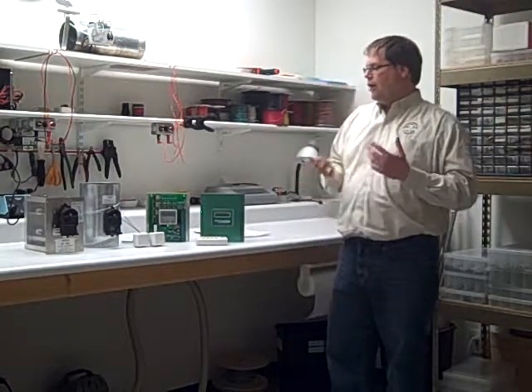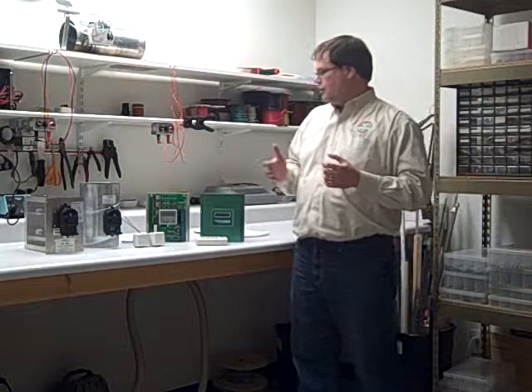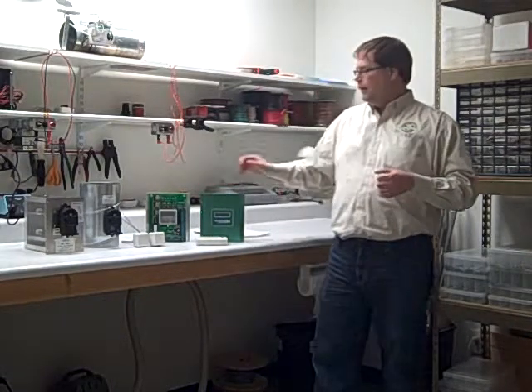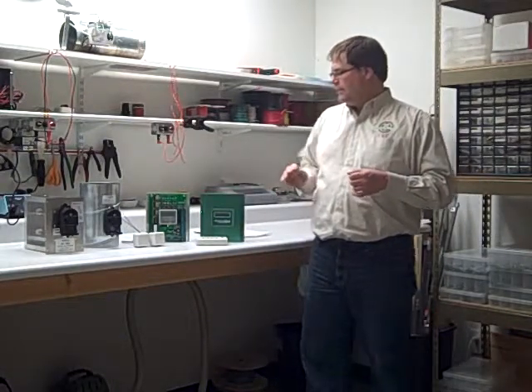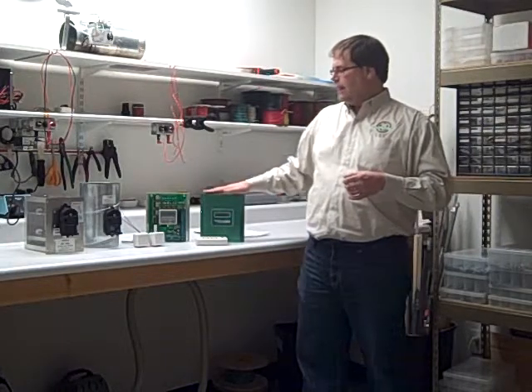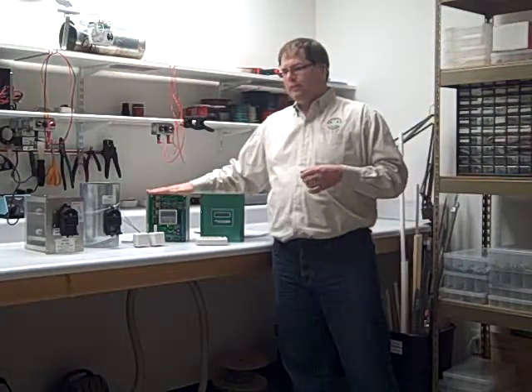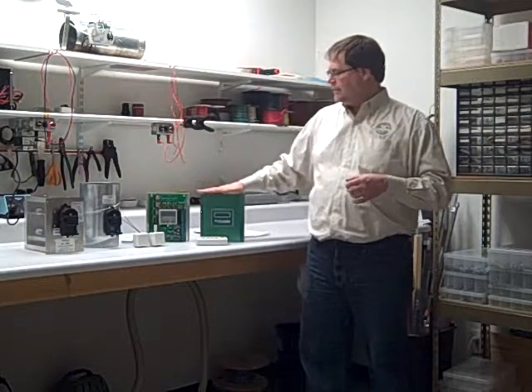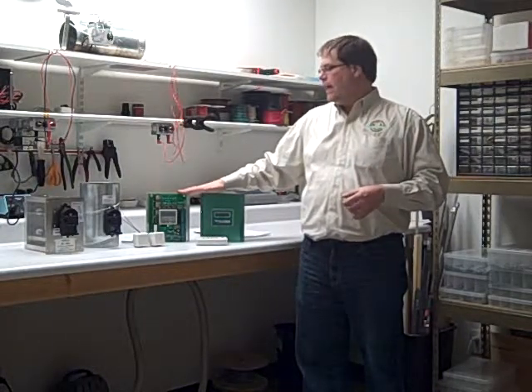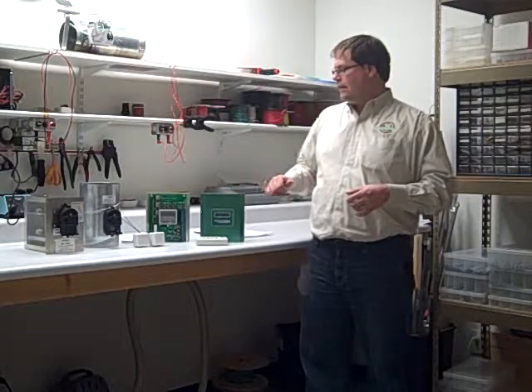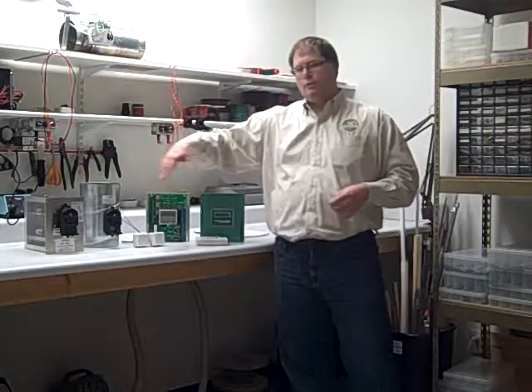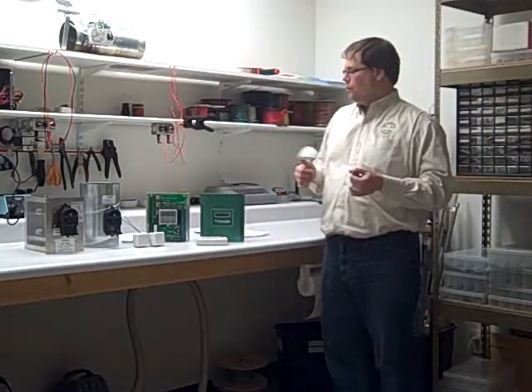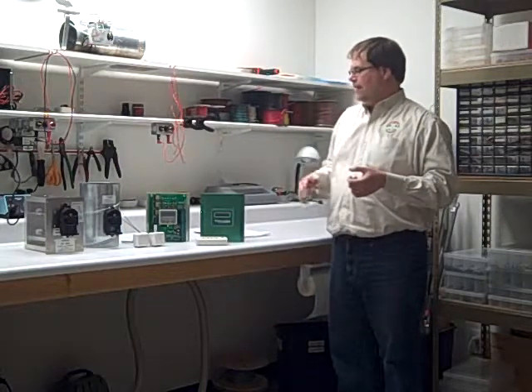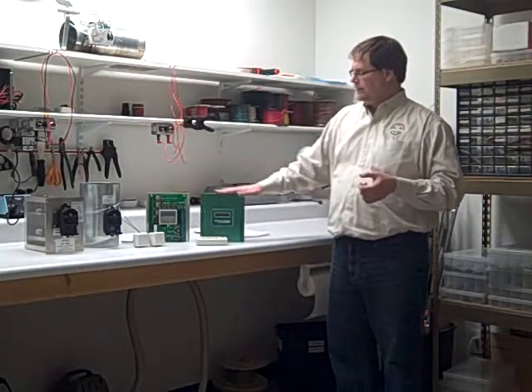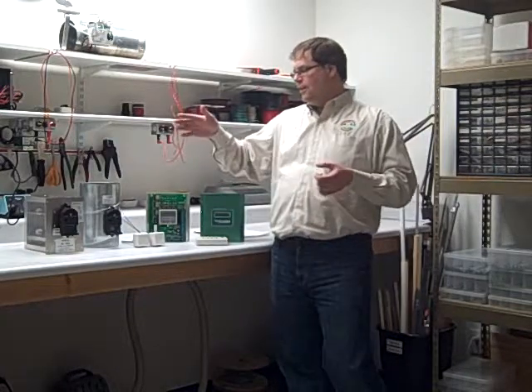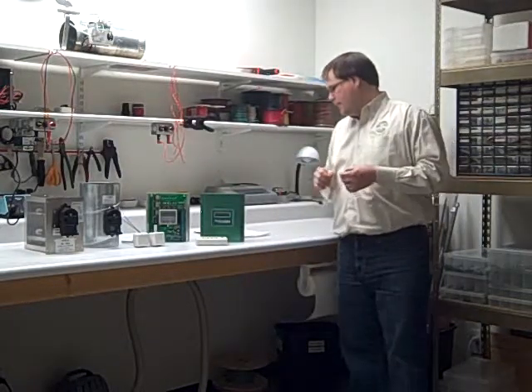If you had a larger home or a commercial facility and you needed multiple wireless comfort Z600s in there, you can actually address the panels themselves with a different number. So you can have up to 6 of these in one facility, and you don't have to worry about there being any interference between the panels themselves or their corresponding dampers. So it's a pretty cool deal. You could technically have 6 times 6. You could have 6 panels, and each panel can have up to 6 zones. So you could actually have 36 zones in the facility.